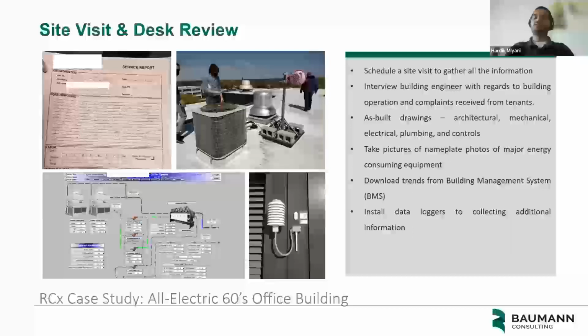So once we have the drawings, we verified whether all those equipments are still existing in this building or not. There are high chances that over a period of time, they might have upgraded their equipment. So that is the place where we do the audit, where we take the nameplate photos of each and every equipment and later on verify whether it matches with the as-built drawings or not. So the nameplate photos not only help us for all the engineering calculations as part of the investigation phase, but it also helps us to coordinate with the equipment representative for getting additional information for the building.